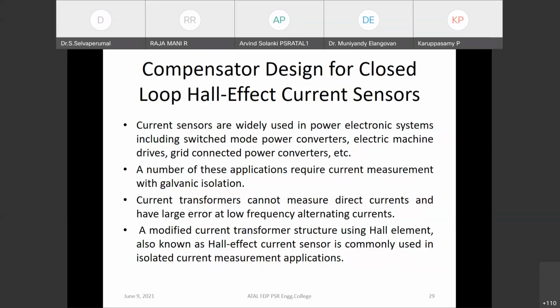An equivalent circuit is derived using some practical assumptions which facilitates the analysis of these sensors. Closed form analytical expressions of step response are derived for the current sensor with proportional and PI compensators, showing the effect of control parameter design on dynamic performance. Based on these expressions, a procedure is devised to tune the PI compensator parameters for high precision current measurement. A prototype current sensor is built in the laboratory and tested to validate the analysis.